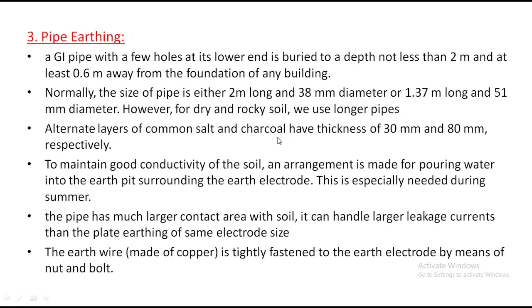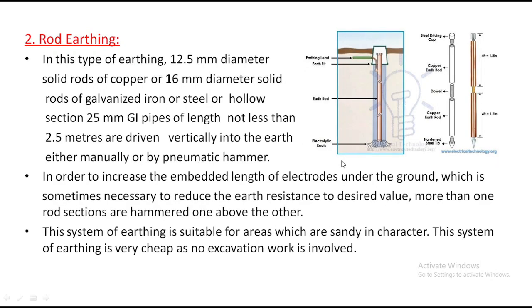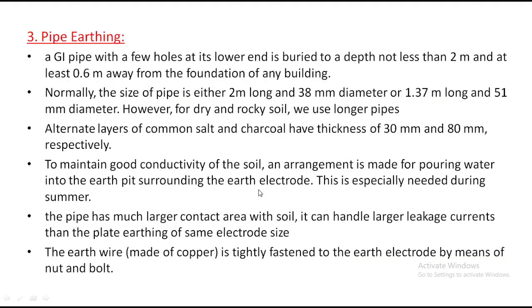Alternate layers of common salt and charcoal have thicknesses of 30 mm and 80 mm respectively. We use first salt and charcoal at 30 mm and 80 mm like that. To maintain good conductivity of the soil, an arrangement is made for pouring water into the earth pit surrounding the earth electrode. So we have to pour the water to maintain the conductivity, because water has more conducting property. That's why we get a shock whenever a short circuit occurs there. This is specially needed during summer. In the summer we require this.